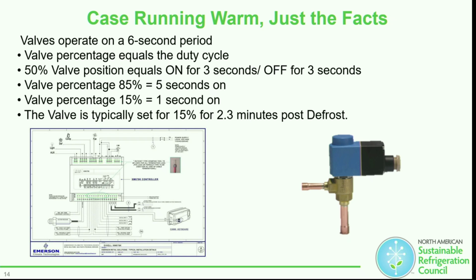The valve is typically set for about 15% for 2 minutes and 30 seconds for post defrost. This is just to get the initial flow through that coil. So we want to remove all the heat that we just added to that unit by putting it into a defrost.